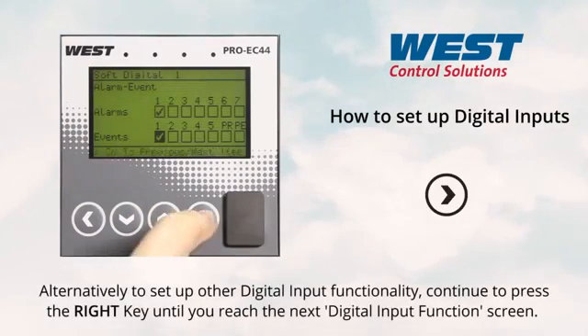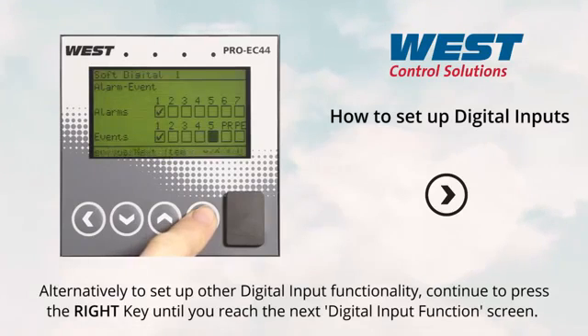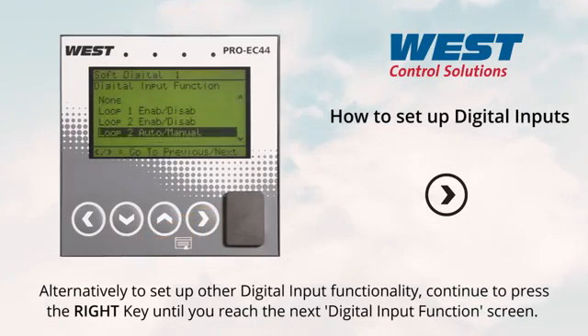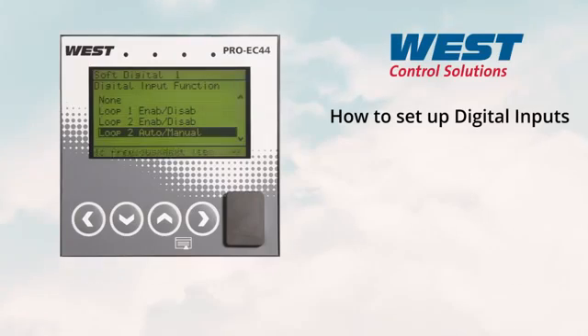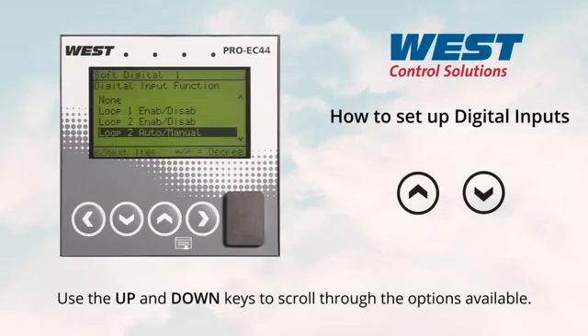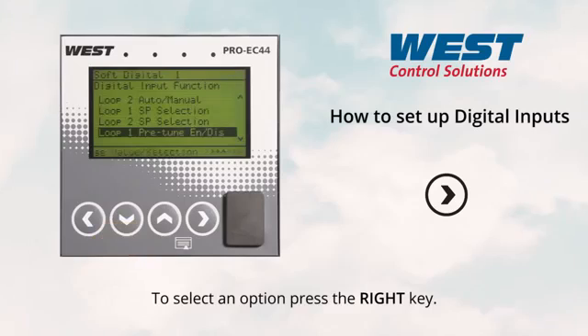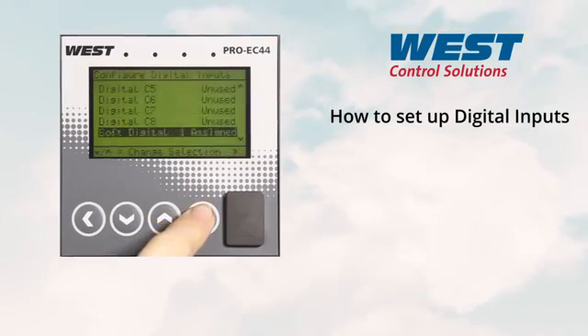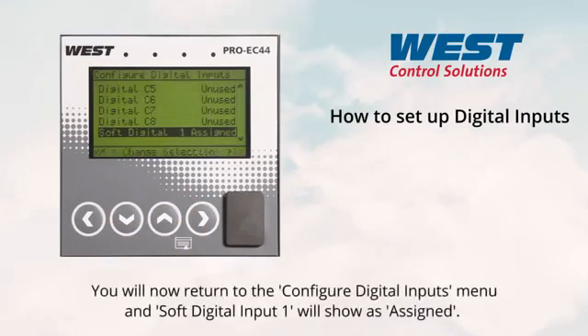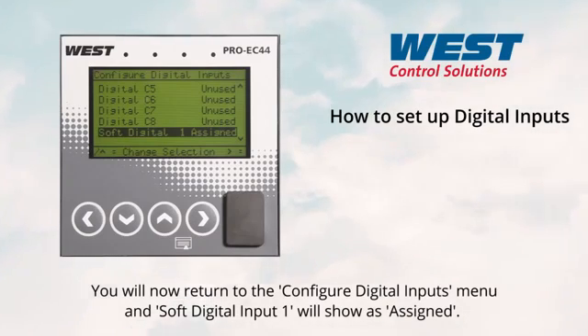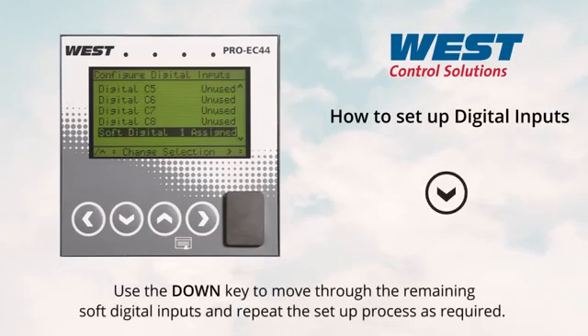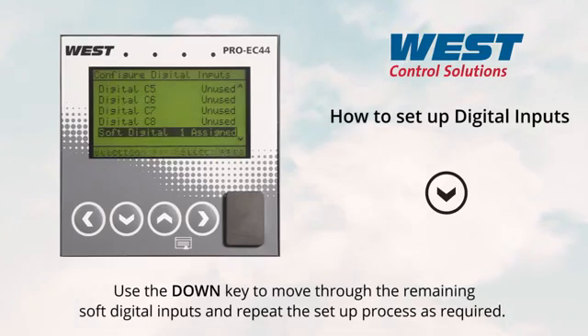Alternatively, to set up other digital input functionality, continue to press the right key until you reach the next digital input function screen. Here, use the up and down keys to scroll through the options available, then press the right key to select an option. You will now return to the configured digital inputs menu and soft digital input 1 will show as assigned. Use the down key to move through the remaining soft digital inputs and repeat the setup process as required.